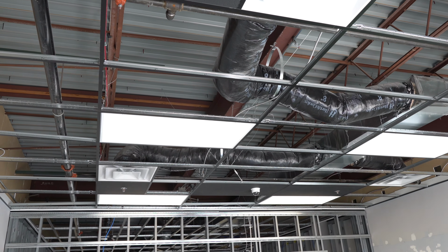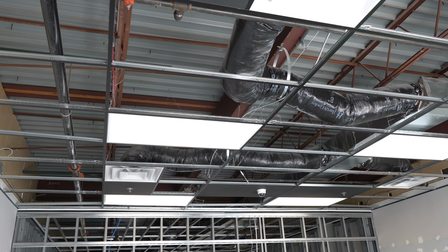For low voltage, you don't have to use a licensed electrician, and inspections and standards aren't quite as rigorous, but there are standards. I'm following those on this install, like using this plenum-rated cabling in the open space above the ceiling. In my studio, the plenum is part of the HVAC air return, so cables need to not emit toxic fumes straight into the blower if there's ever a fire.